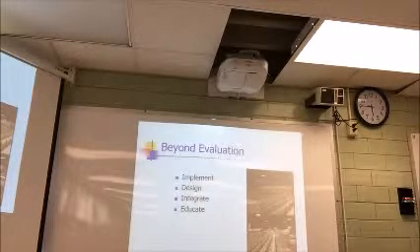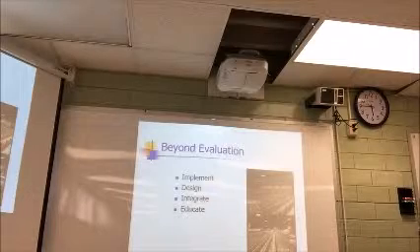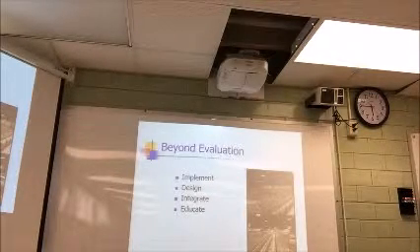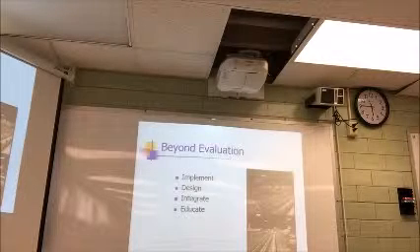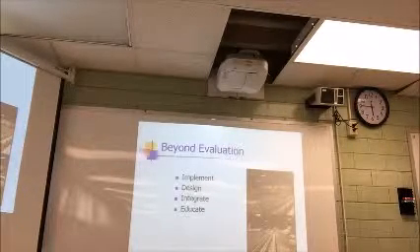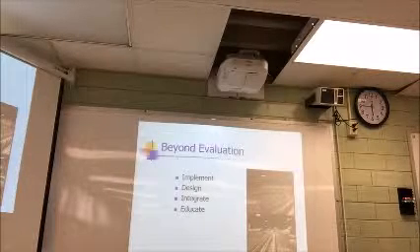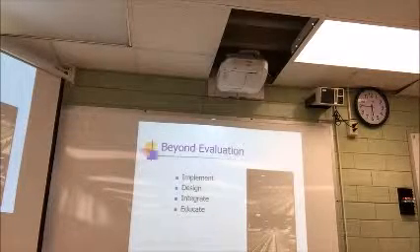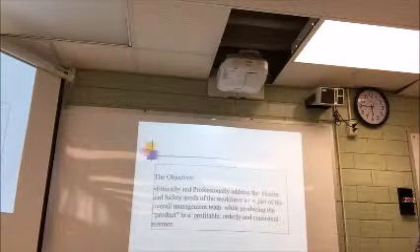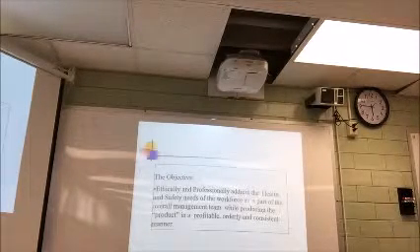I just told you one of the almost major mistakes I made. And one time I couldn't stop it with the ventilation or the capture system in the sugar plant. They said, oh no, it'll work. We got in there, we didn't have enough makeup air. Guess what? It did not work. So industrial hygiene management, again, we want to protect people.